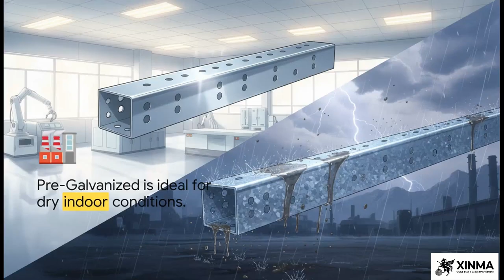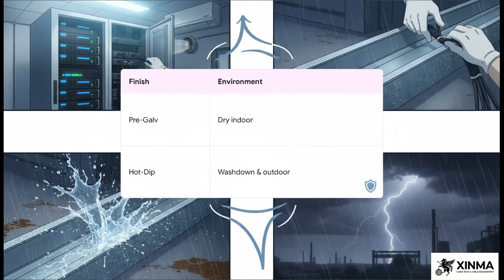Section 2, pre-galvanized versus hot dip. This is the core engineering trade-off, and the absolute focus for you procurement folks. You aren't just comparing two products, you're comparing two entirely different survival profiles. Pre-galvanized sheets are cut and punched during manufacturing, which leaves those raw steel edges completely exposed. If you try to save a few bucks by throwing that into a wet environment, you are looking at a total system disaster down the line. It's all about matching the precise chemical protection to the physical reality of the site.